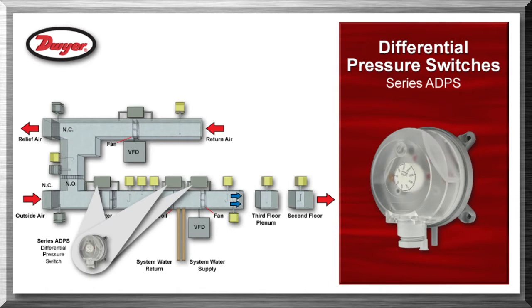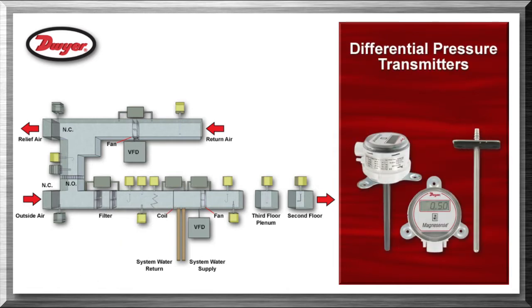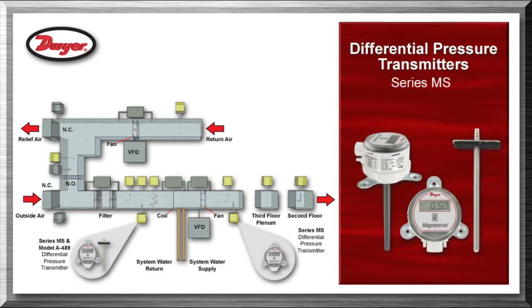Differential pressure switches series ADPS are used as a frozen coil alarm by monitoring the pressure loss across the coils in the duct to indicate a frozen coil condition. They are also used as a dirty filter alarm by monitoring the differential pressure across the filter. Differential pressure transmitters series MS are used with a static pressure sensor such as the model A-489, or with an inherent static probe, to monitor discharge air and mixing air duct static pressures.